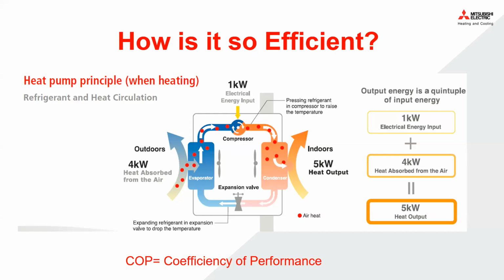What makes the heat pump that much more efficient is that the refrigerant does most of the work. The electricity simply runs the compressor and the fans. How we recognize this is called COP, which is the coefficient of performance. Basically what we're saying is, how much heat energy do you get out for how much energy you put in? So this drawing here is saying that you put in 1 kilowatt of electric input, and then you take in 4 kilowatts of energy from the outside air, and your output is 5 kilowatts. Theoretically, this would be a COP of 5. If we compare that to traditional systems, if you have a 98% efficient furnace, that's a COP of 0.98.